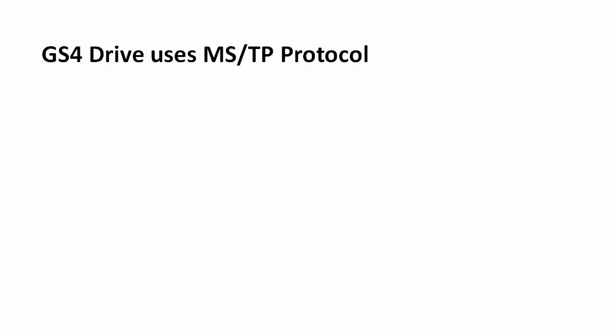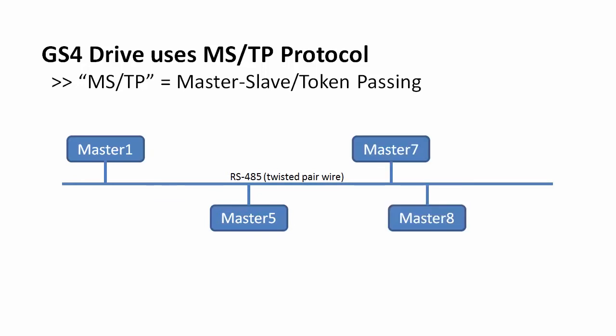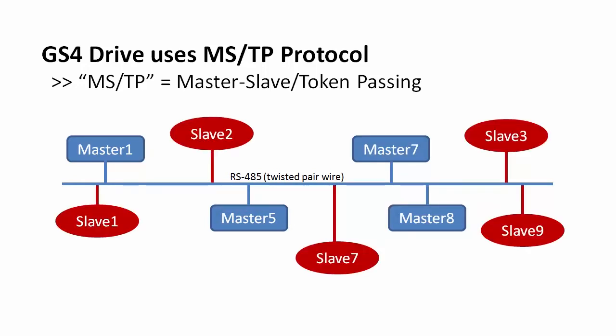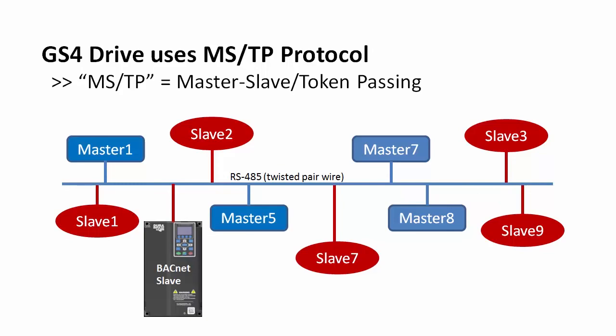One side note: the GS4 drive supports MSTP protocol — that's master-slave token-passing over the RS-485 network. All that means is you have a bunch of BACnet master controllers and slave devices on your RS-485 network. The lowest-addressed master queries any devices it wants to talk to. When it's done, it passes control to the next highest-addressed master, and so on. Only masters can initiate conversations on the network, and only the currently active master — the one with the token — can speak. Slave devices can only respond to requests; they can't generate them. The GS4 drive is a slave on the BACnet MSTP network.